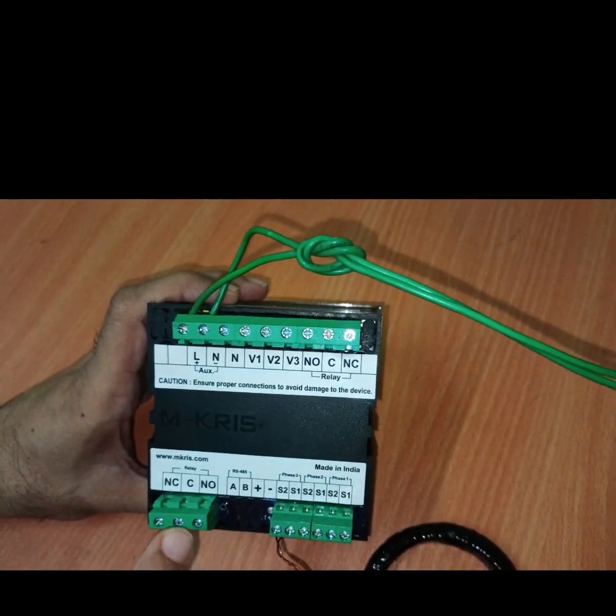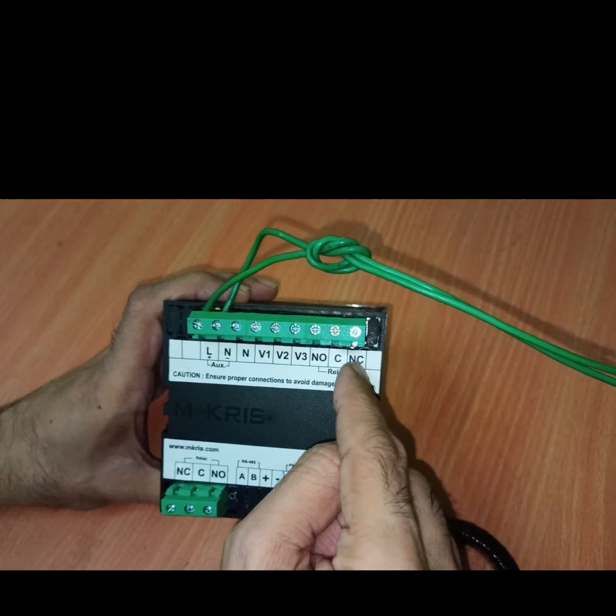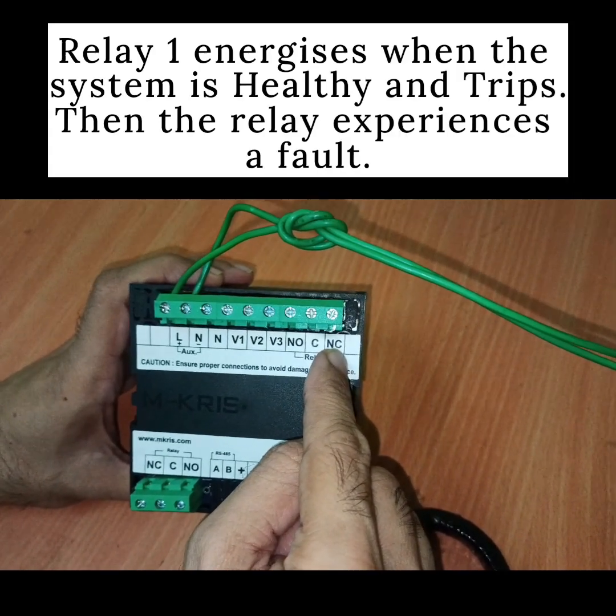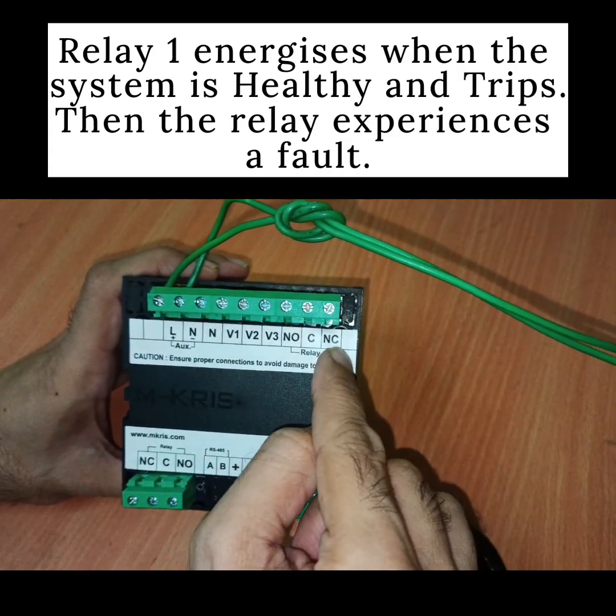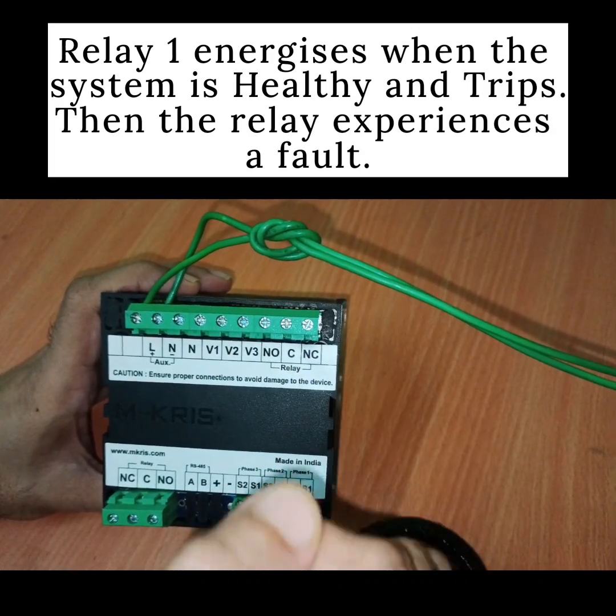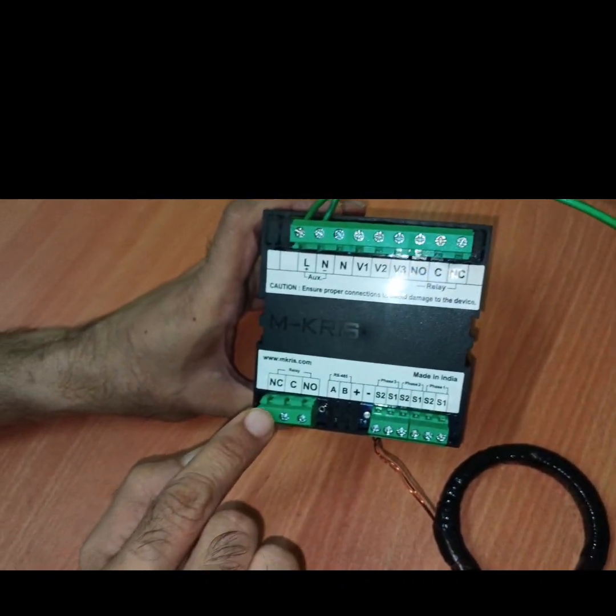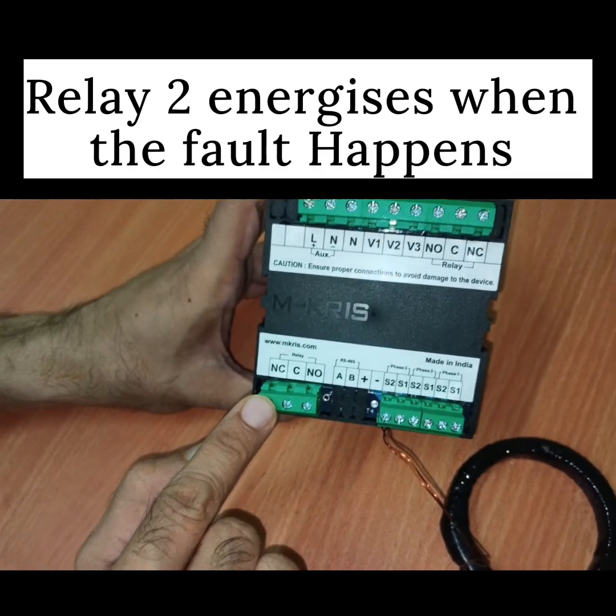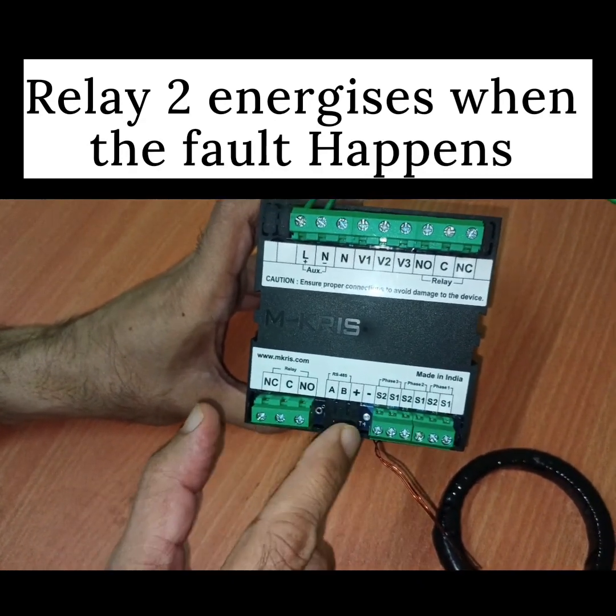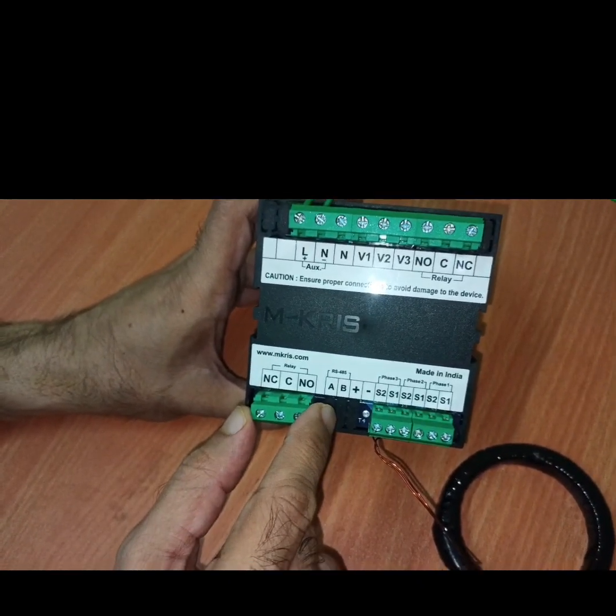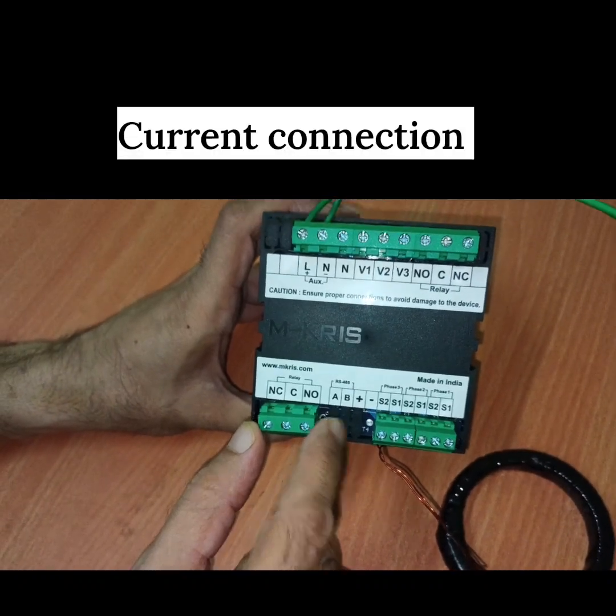There are two relays provided. This relay energizes when the system is healthy and trips when the relay experiences a fault. This relay becomes energized when the fault happens. So this relay can be used for annunciation purpose, fault annunciation purpose.